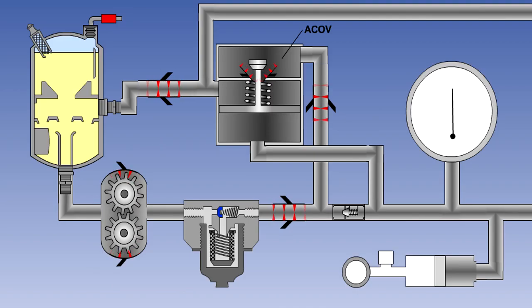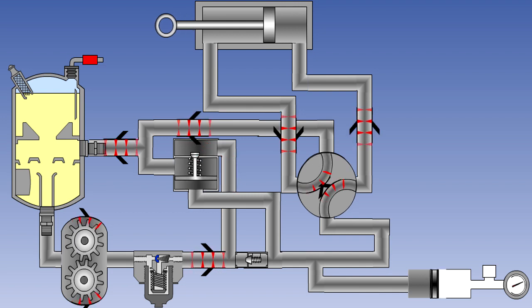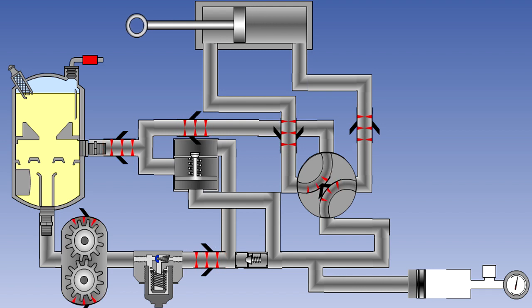If the system is using a constant delivery fixed volume type pump with an automatic cut-out valve, it will prolong the period between cut-out and cut-in of the automatic cut-out valve, and so reduce the wear on the pump. Operation of the automatic cut-out valve will be explained shortly. The accumulator will also provide the initial fluid when a selection is made and the pump is cut out, or at minimum stroke. If a service is selected, a supply of fluid under pressure is available until pressure drops sufficiently to bring the pump online.